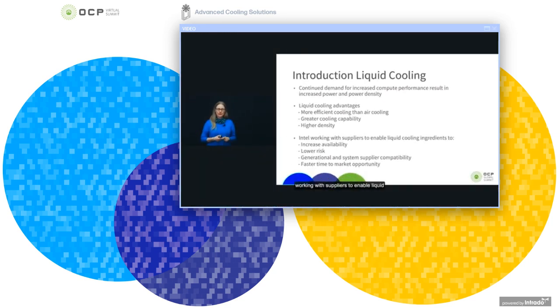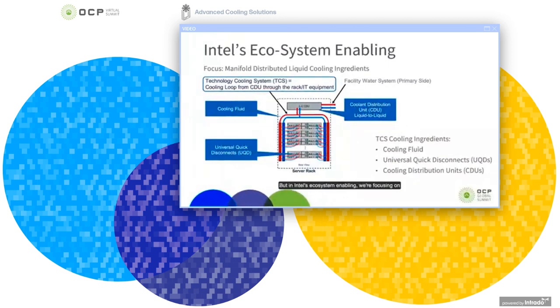So Intel is working with suppliers to enable liquid cooling ingredients to really increase the availability. So when liquid cooling is needed to cool the high power components, the ingredients should already be there in the ecosystem. This also lowers the risk for liquid cooling solutions, and can also allow for generational and system supplier compatibility, which is something that Mark will be talking about when it comes to universal quick disconnects. And it can also allow faster time to market opportunity if all the ingredients are already in place within the ecosystem.